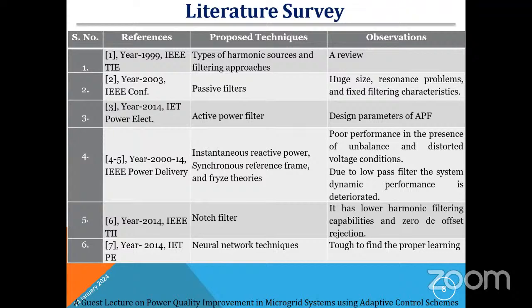But because the grid is not stable, the voltage may be high or low based on the loads you are connected to. Suddenly loads will be disconnected, suddenly a load will be added to the grid. So based on these high switching characteristic loads, what will happen? The current or voltage harmonics will be high.